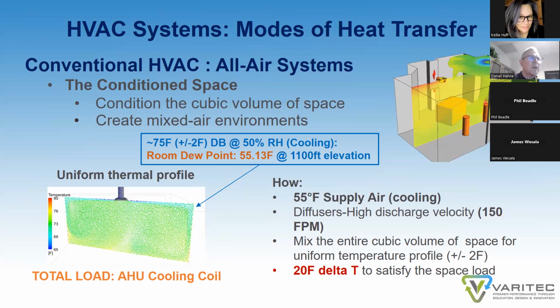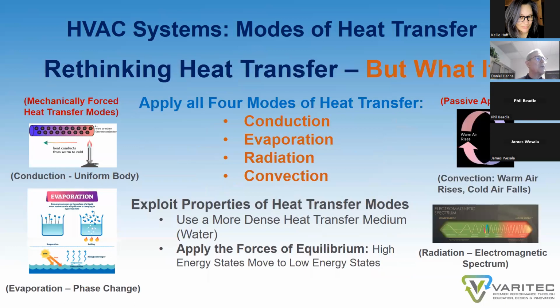That air is injected at high velocity into a room at 150 feet per minute to create a thoroughly mixed environment. So you want to make sure that the air within the space is thoroughly mixed within plus or minus 2 degrees. To do that effectively, a 20-degree delta T is required. It is a 20-degree temperature differential between the air entering a room at 55 and a room set point at 75 degrees. And this 20-degree delta T, I ask that you keep in mind for later in this presentation, because you're going to see the difference of what passive radiant solutions offer by using chilled water as the heat transfer medium.